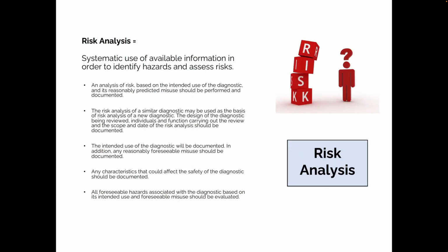So risk analysis is the systematic use of the available data in order to identify hazards and assess risks. It's based on the predicted use of the diagnostic and how it could be misused. You can base that on a similar device, so you don't always have to start from scratch. You can use a similar device as your template. The design of that device and its use should be reviewed by individuals who are close to the situation, in terms of how it's manufactured and how it's used. It needs to be documented in terms of foreseeable misuse.